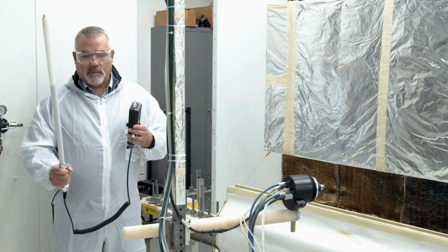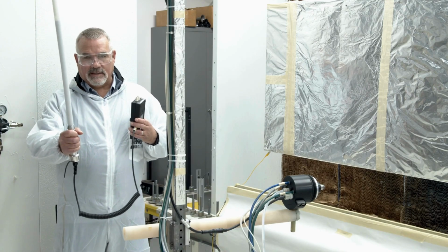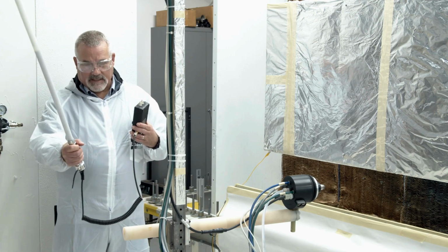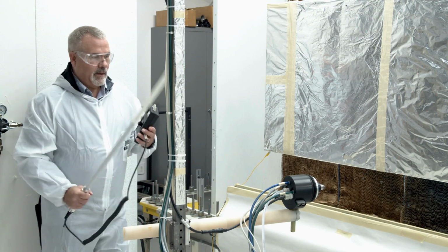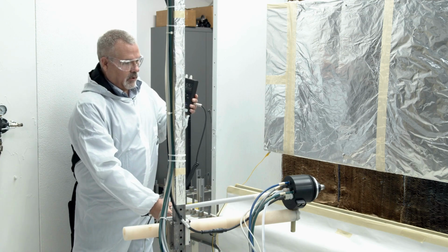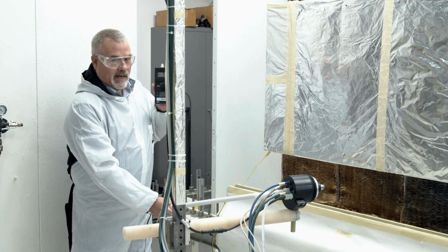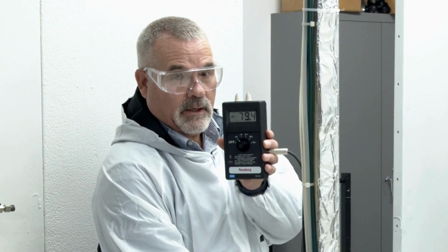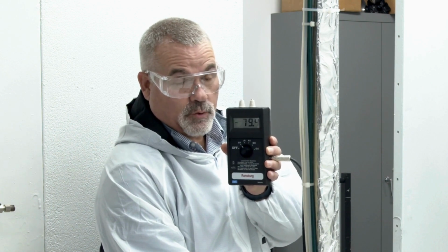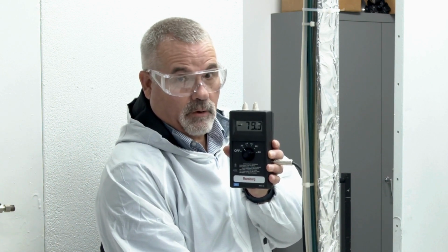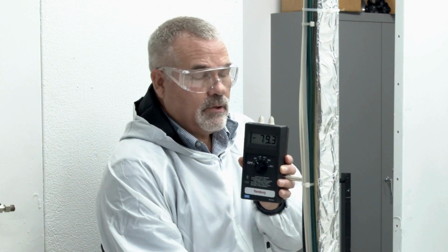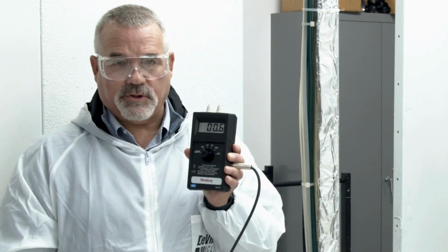To make the proper measurement, make sure you have skin contact with the metallic portion of the probe. Then you take and lightly touch the probe to the end of the applicator with voltage on, and you'll get a reading. It should be within plus or minus 2 to 3 kV of your actual reading. You can use this information to troubleshoot your system.